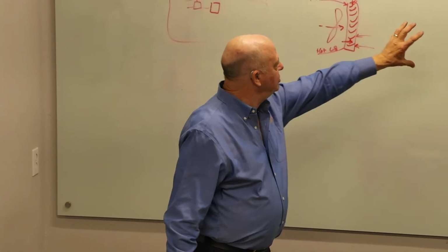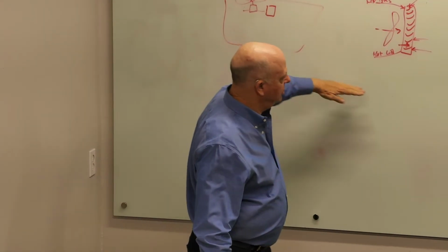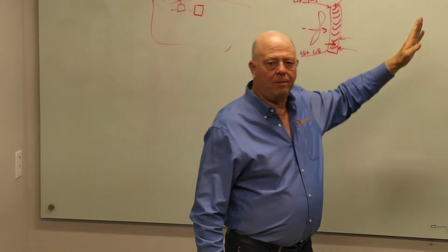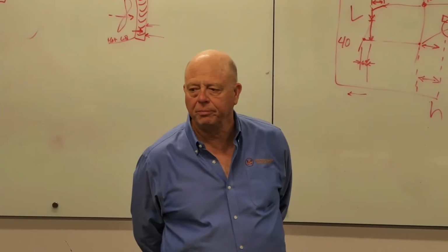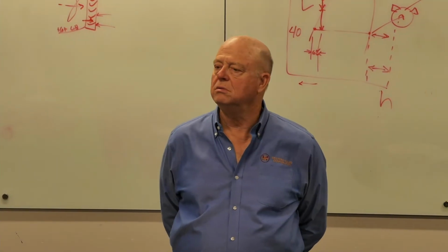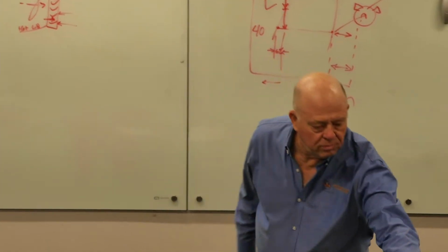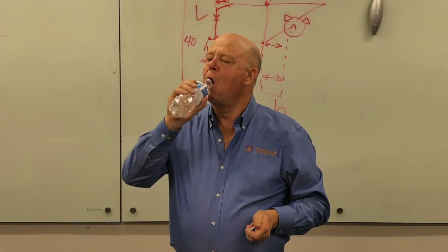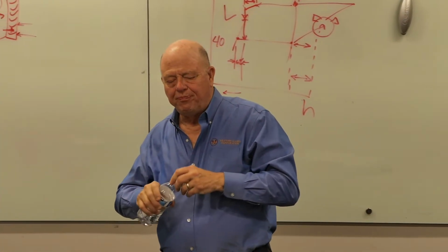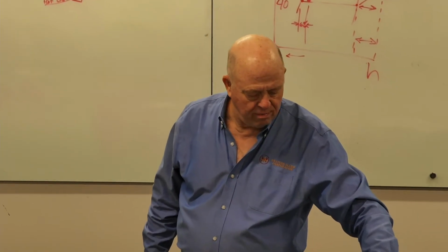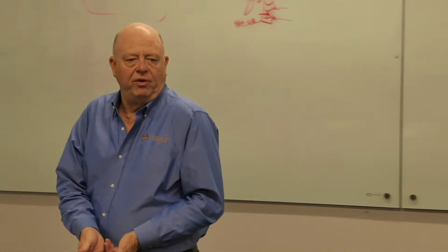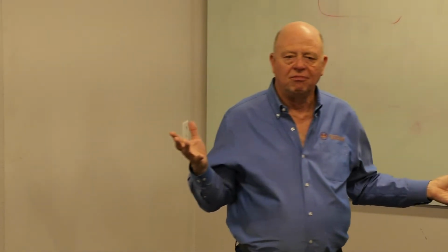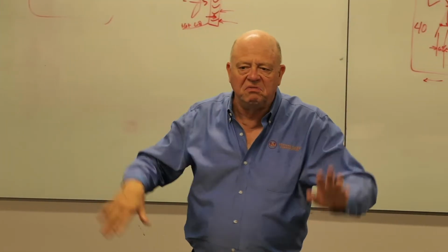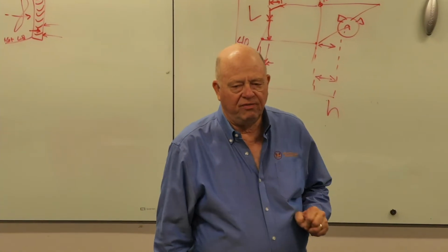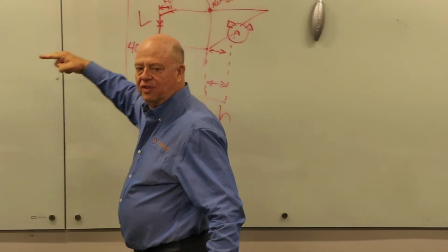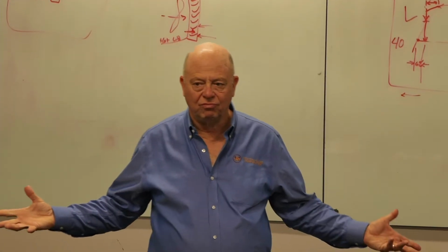So, speculation now. We've got a condensing unit, we've got an air handler, we've got a suction and a liquid and hot gas line, right? Why would you not want to bury refrigerant lines? What occurs to you? There's more than one reason. Oh, come on, what's the temperature of the ground? Anybody got an idea of what the temperature is in the earth 6 feet down? Southern California, 55, 65, like that. If your unit's off long, what happens to the gas in the gas line? Condenses, right?